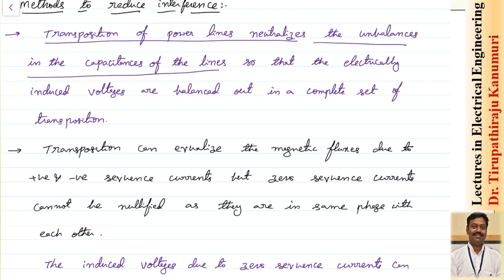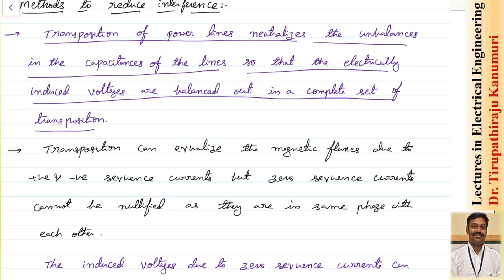If the capacitances are equal, the respective charges passing through each phase are displaced by 120 degrees, so they will nullify each other if you transpose the transmission lines. The electrically induced voltages are balanced out in a complete set of transposition. Transposition ensures the distance from each conductor to the communication line becomes equal, so capacitances get equalized in all the lines.